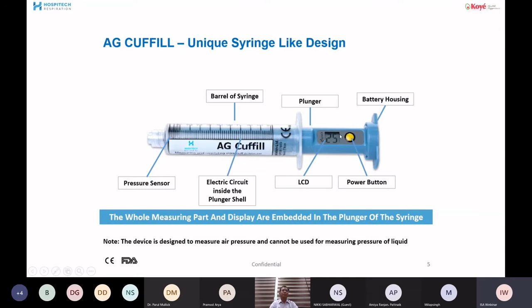And it is very easy to use as well. All you have to do when inflating is pull back the plunger, switch on the device by pressing this yellow button, connect to the pilot tube and start inflating. As you start inflating, you can see the real-time pressure of the endotracheal cuff, and you can stop inflating at the desired level. Now, based on discussions with various anesthesiologists, for adults, the desired pressure is between 20 and 30 centimeters of water. And for children, the desired pressure level is 15 to 20 centimeters of water.